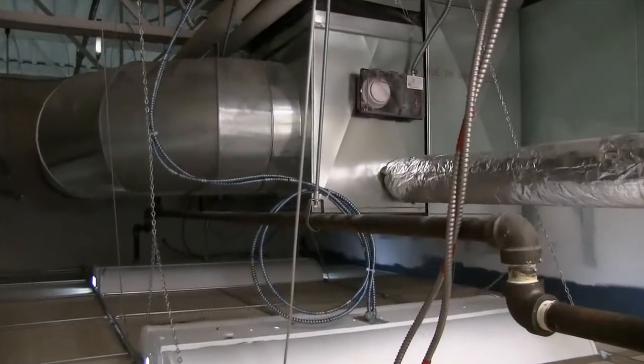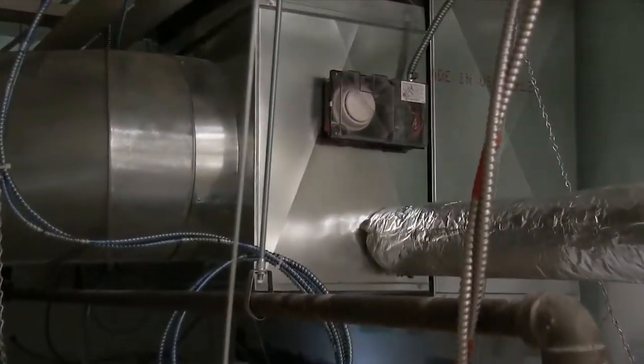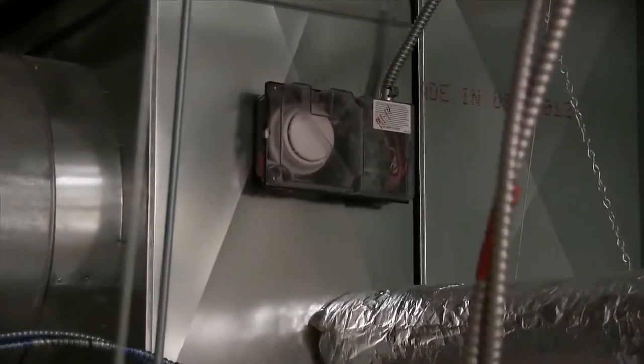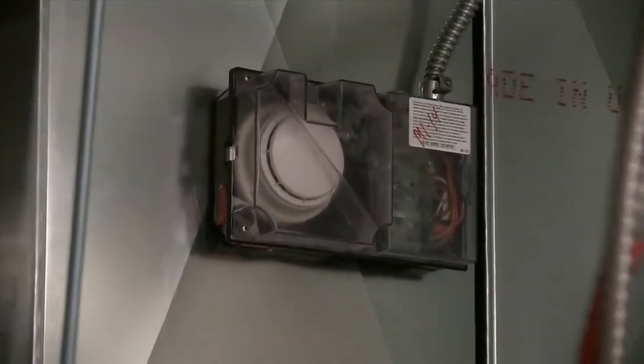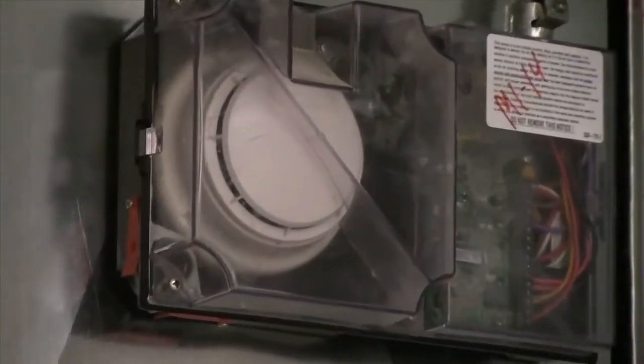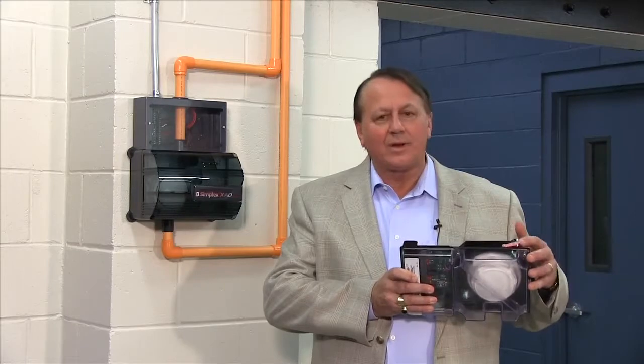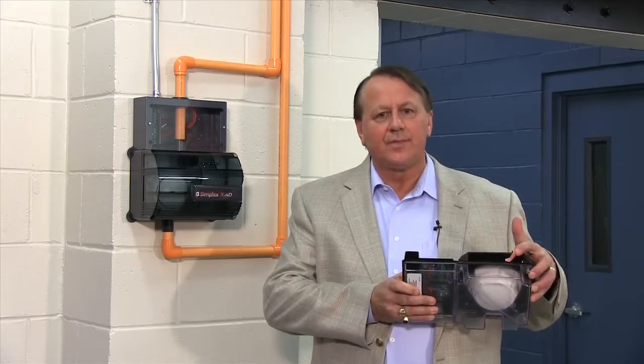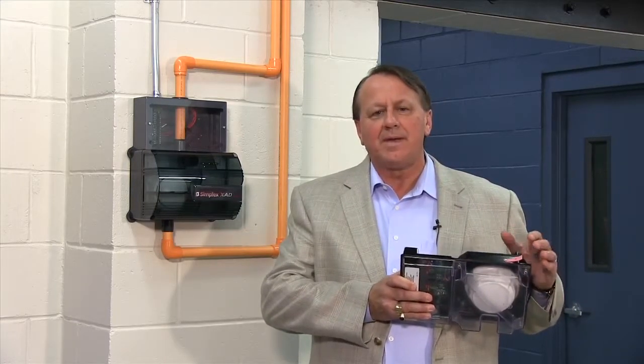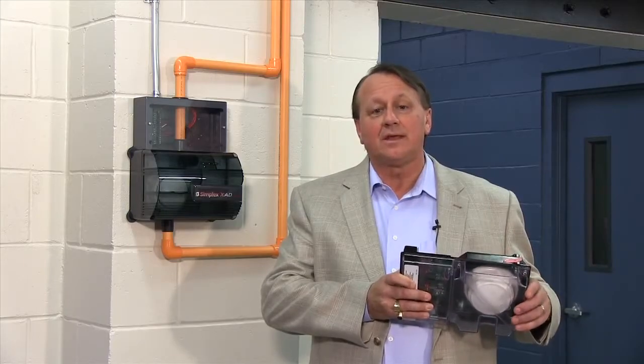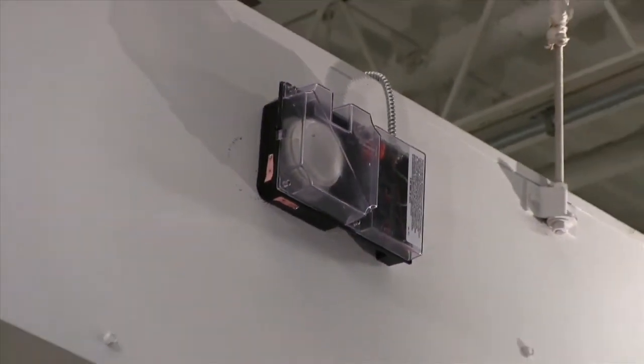Mounting duct detectors directly to the duct can create challenges in accessibility for testing, service, and maintenance. You can see that this duct detector has a test port where canned smoke can be introduced. Pretty straightforward, but imagine this unit mounted onto a duct that is above the ceiling and difficult to get to.